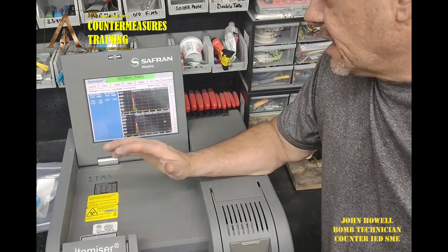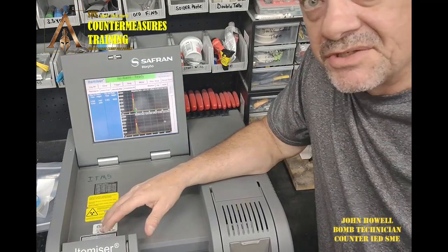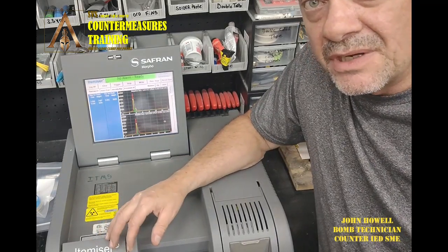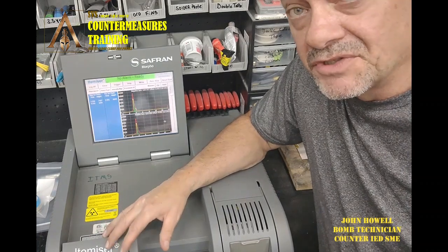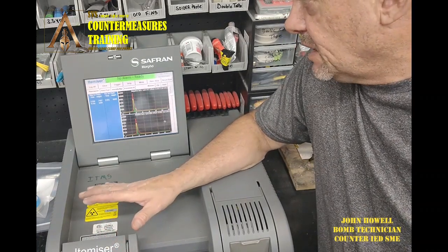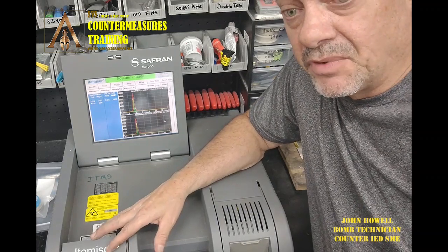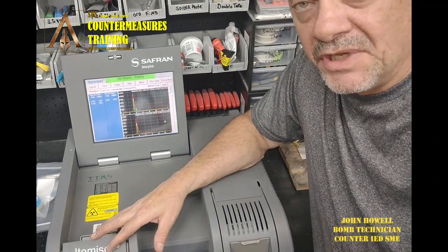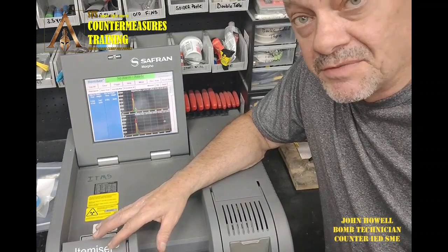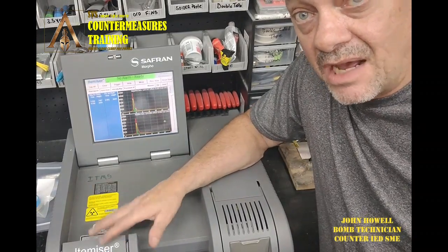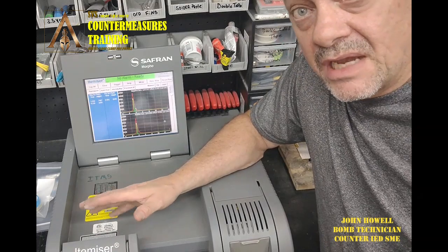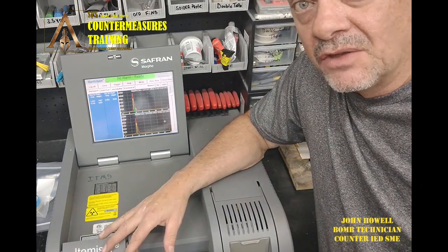So this is an Itemiser explosive trace detection system. It uses a technology called ion trap mobility spectrometry. And pretty much all of the explosive trace detection systems that are deployed by the airports are going to be using an IMS, ion mobility spectrometry type technology. Now there's different ways they do that. We're going to go over that and explain how all of that works.